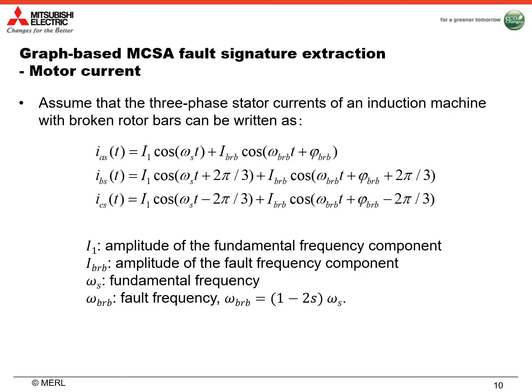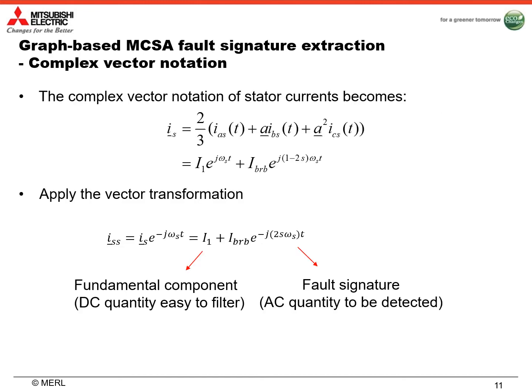To introduce our proposed graph-based MCSA fault signature extraction method, let's assume we have obtained the motor current by either experiments or simulations. For an induction machine with broken rotor bar fault, the three-phase stator current can be expressed using these equations, where I1 is the amplitude of the fundamental frequency component, and I_brb is the amplitude of the fault frequency component. Omega_S is the fundamental frequency and Omega_B is the fault frequency component. Once we have the three-phase stator current, we can use complex vector notation to represent it. By applying the vector transformation, we can convert the fundamental component into a DC quantity, which is easy to filter out, and the fault signature remains as an AC quantity.